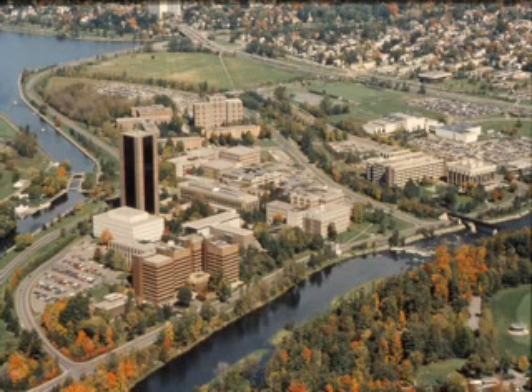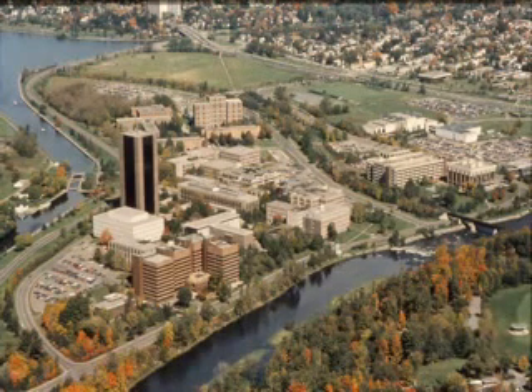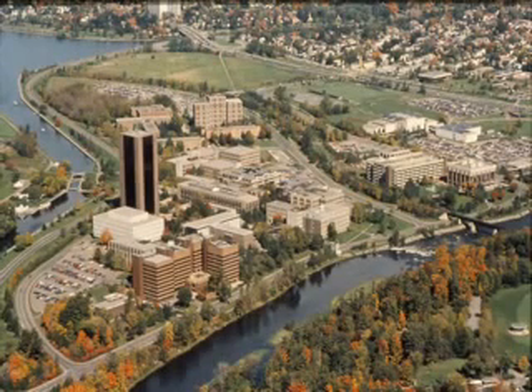That building had a high heat load, needing a lot of cooling even in wintertime because of all the computers. Of course, the first question was: you've got a river here, a canal and a lake here, why not just use the surface water? Well, the surface water doesn't give you a constant temperature. In wintertime it's close to 0 degrees C, and in summertime it's probably around 20 degrees C. So you don't get that constant temperature, and if you're going to have a differential, you'd want it to go the other way - you'd rather have 0 degree water in summer and 20 degree water in winter. So it doesn't work. Plus there's all kinds of environmental regulations you can get into, so we stayed away from it.